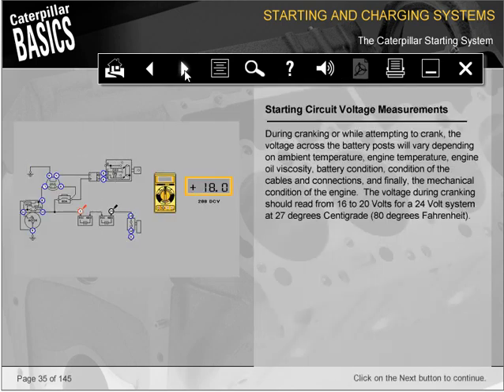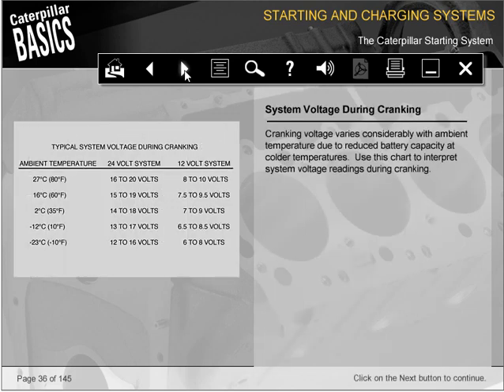During cranking or while attempting to crank, the voltage across the battery posts will vary depending on ambient temperature, engine oil viscosity, battery condition, condition of the cables and connections, and finally the mechanical condition of the engine. The voltage during cranking should read from 16 to 20 volts for a 24-volt system at 27 degrees centigrade, 80 degrees Fahrenheit. Cranking voltage varies considerably with ambient temperature due to reduced battery capacity at colder temperatures. Use this chart to interpret system voltage readings during cranking.